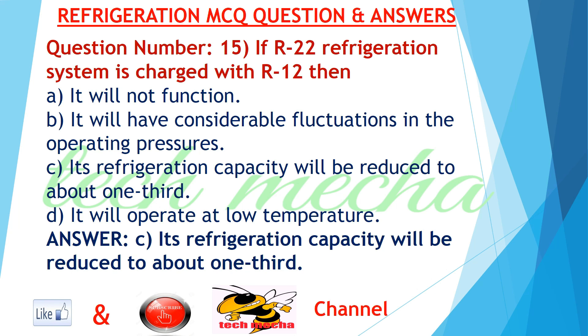Question number 15: If an R-22 refrigeration system is charged with R-12, then A. it will not function, B. it will have considerable fluctuations in the operating pressures, C. its refrigeration capacity will be reduced to about one-third, D. it will operate at low temperature. Answer: C. its refrigeration capacity will be reduced to about one-third.